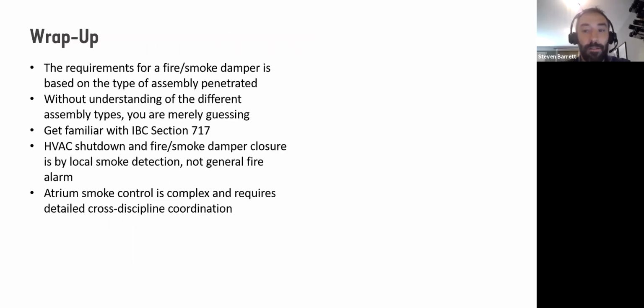Then finally, just to wrap everything up, again, I'll just reiterate that it's really important to know what type of assembly is being penetrated to know whether or not you need a fire, a smoke, or a combination fire smoke damper. And if you don't know the difference between the types, you might just be guessing. You may end up over-specifying, you may end up under-specifying, and could be in a really dangerous situation with life safety. So I strongly encourage you to get familiar with IBC section 717. That's also cross-listed in the IMC, but that's the section on ducts and air transfer openings.